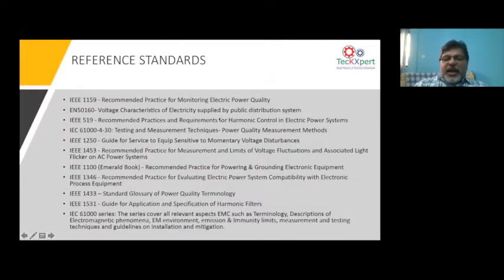Go to the next. Now, I would show this slide. This is the reference standard. So now we can look at it. When you look into power quality, see the number of standards that are there. The IEEE 519, the third standard shown here, is the only one relating to harmonics. The rest of the standards all relate to multiple PQ problems. For example, the 1159 is the major PQ standard. It's followed worldwide.